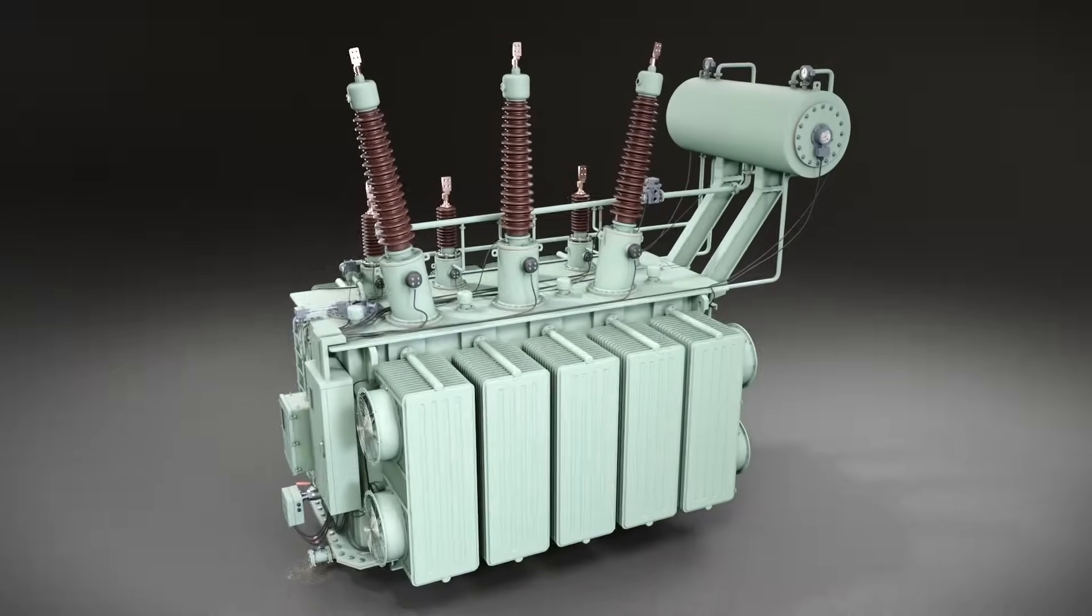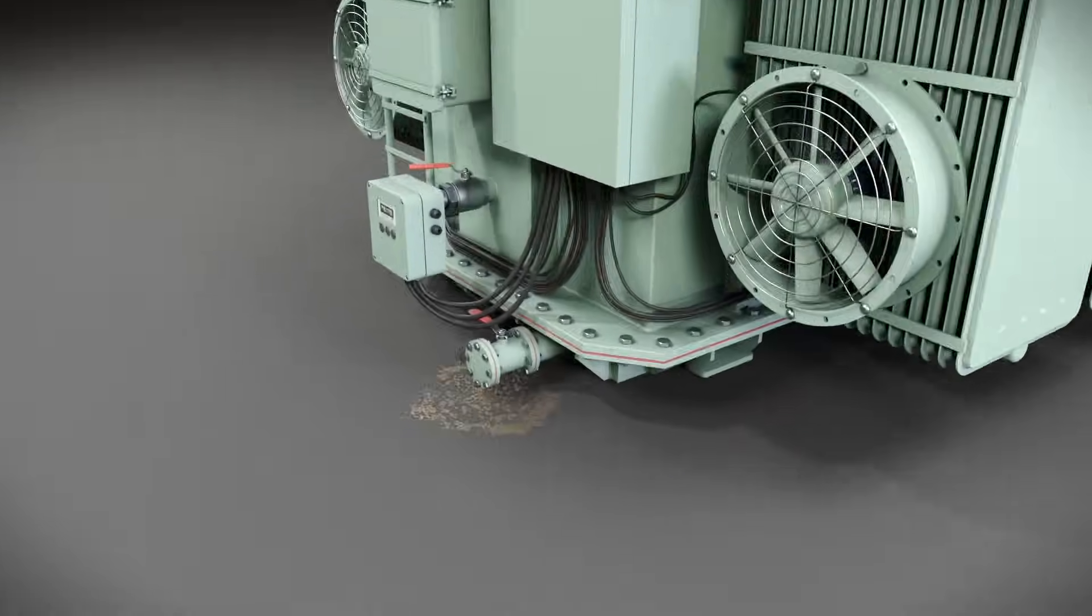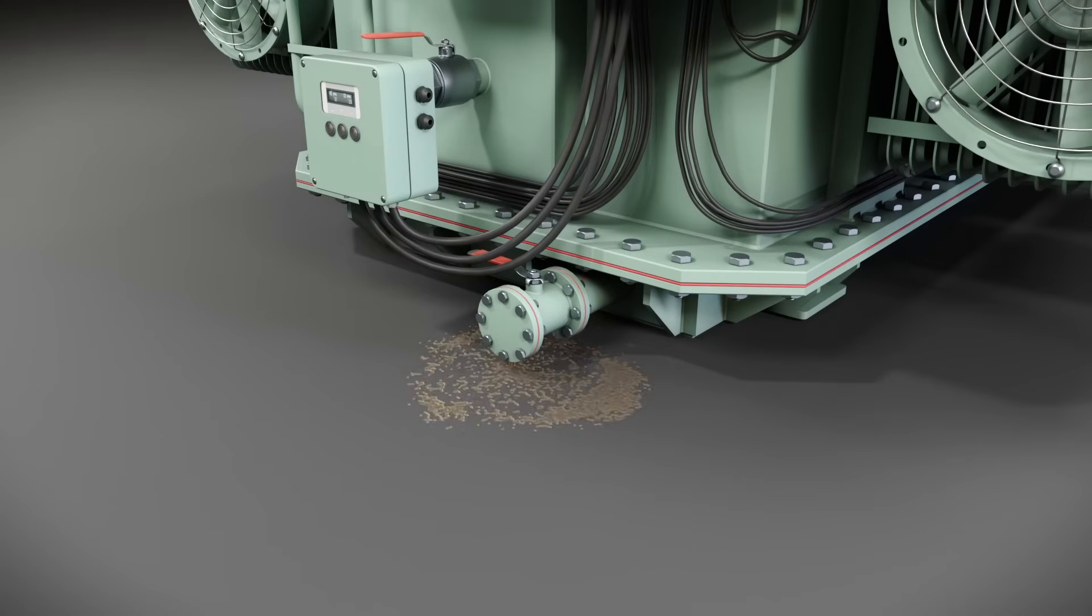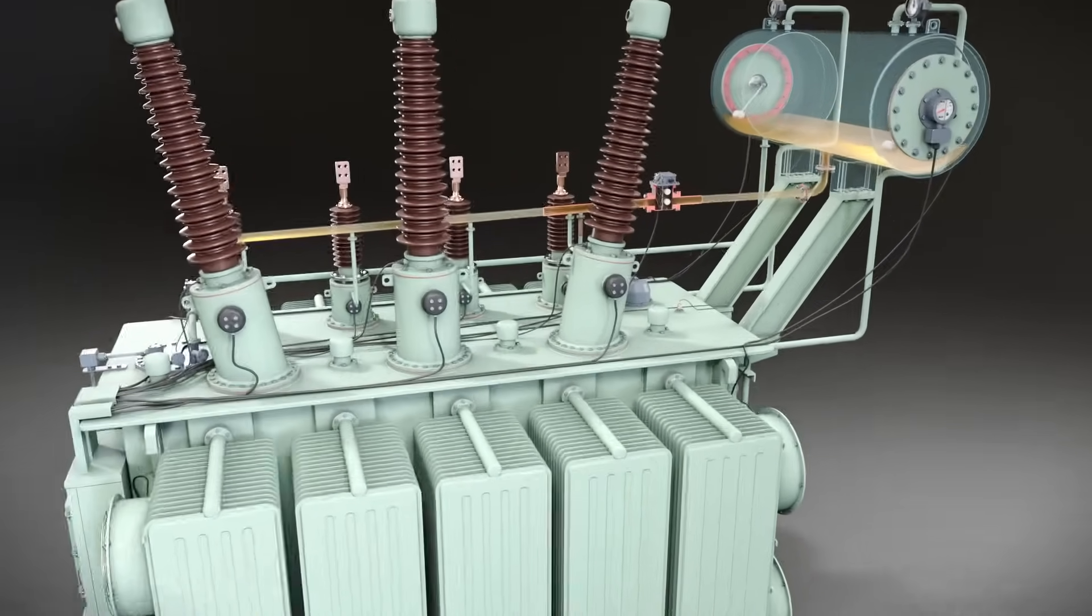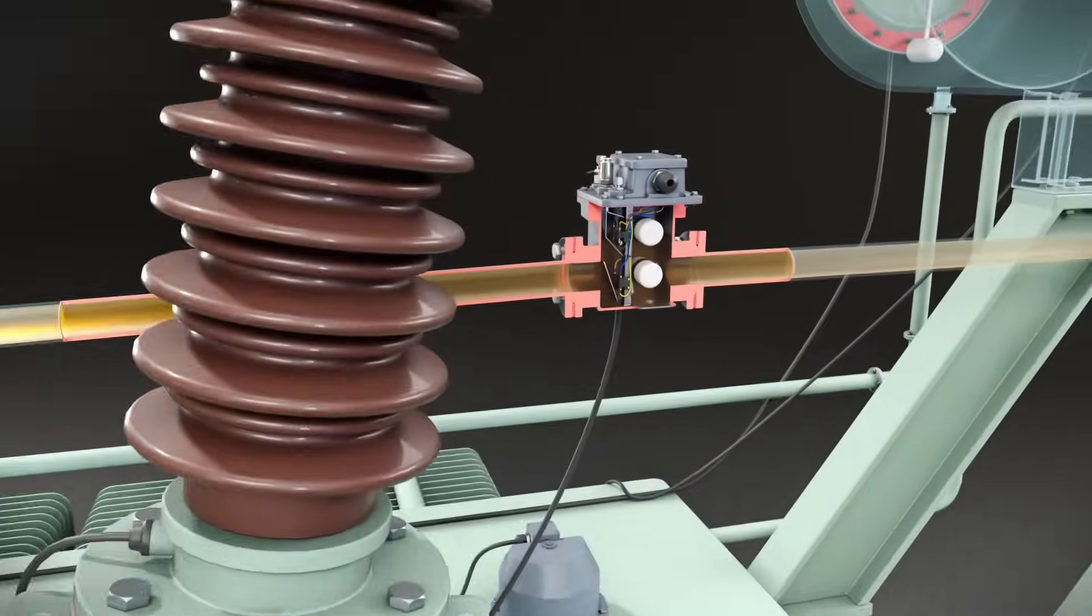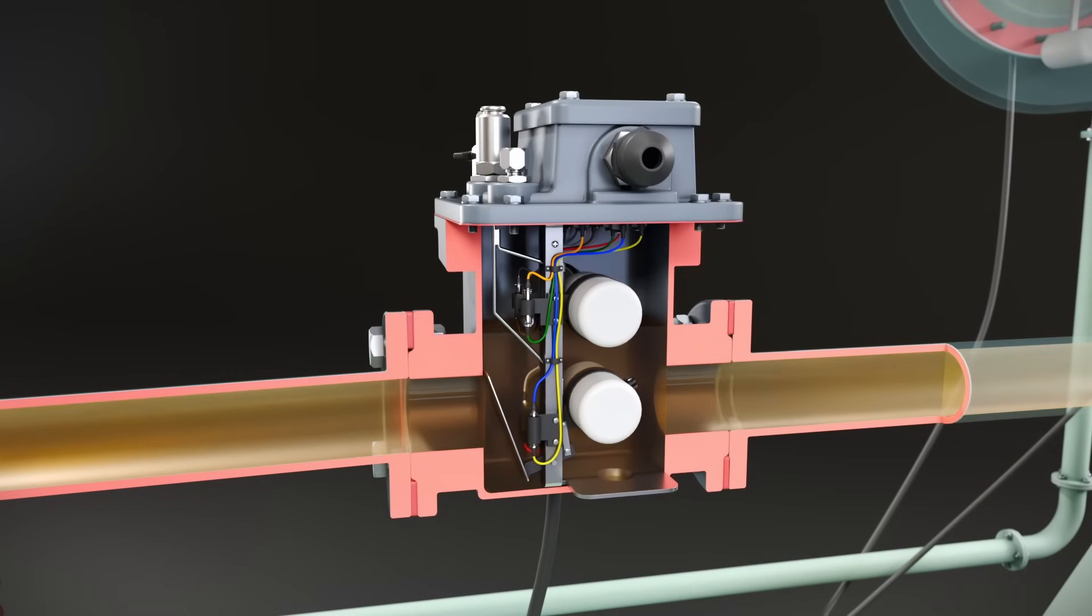Now, imagine a scenario where the oil inside the transformer begins to leak. As a result, the oil level in the conservator starts to decrease, causing the oil level in the Buchholz relay to drop as well. Initially, the upper float responds to the lowering oil level by moving downward, activating its magnetic switch to trigger an alarm signal. This serves as an early warning of a potential issue. If the oil level continues to drop, the lower float will also descend.